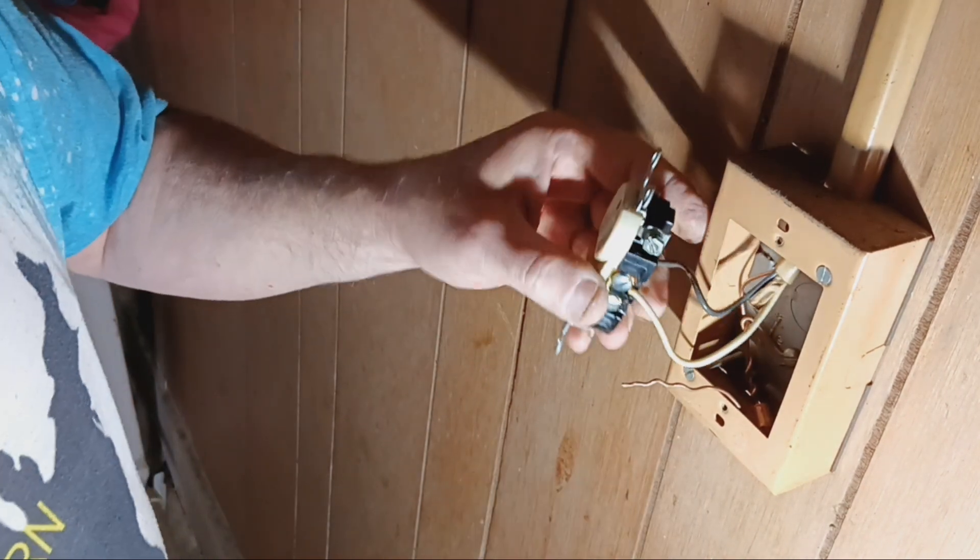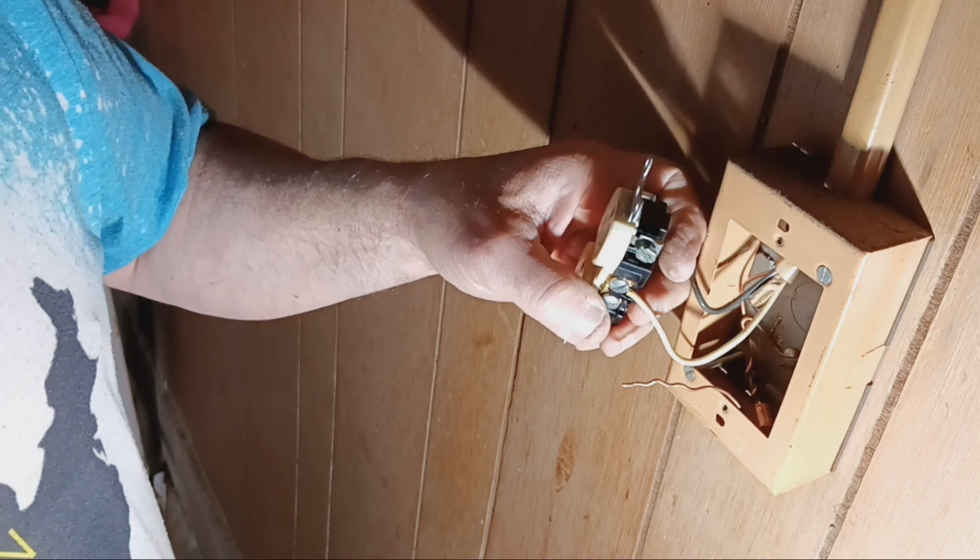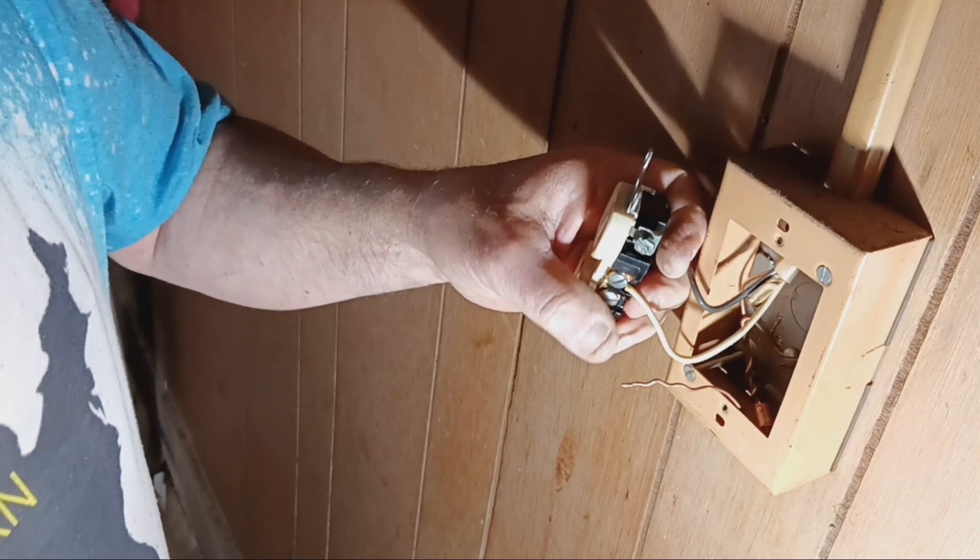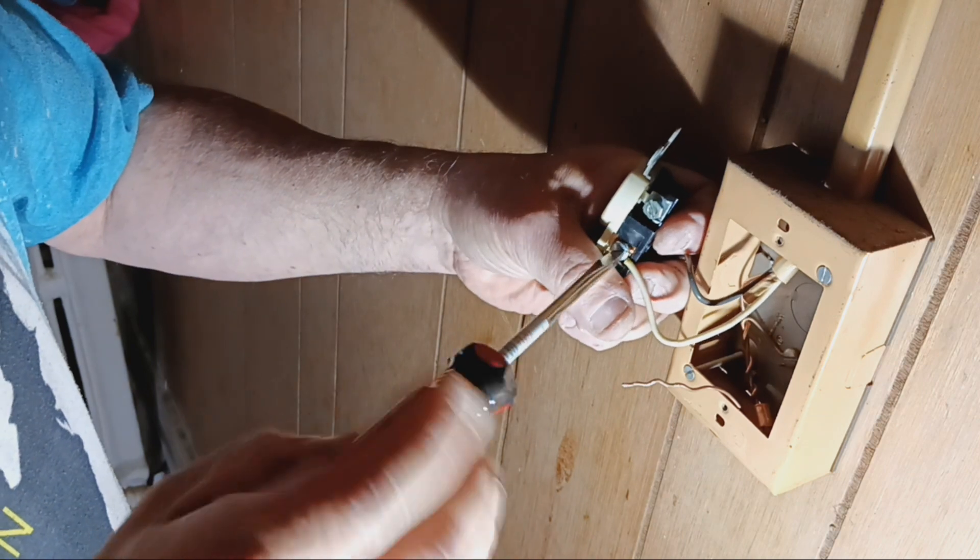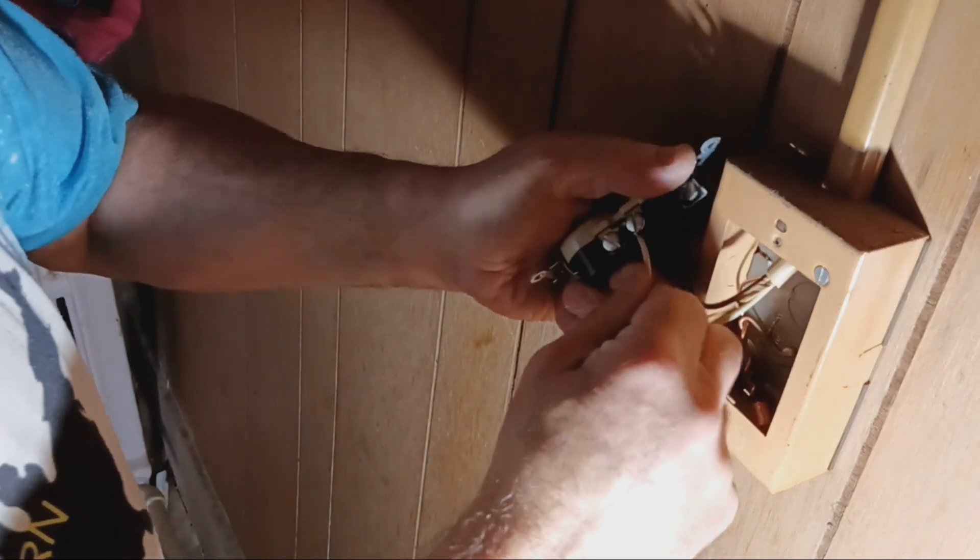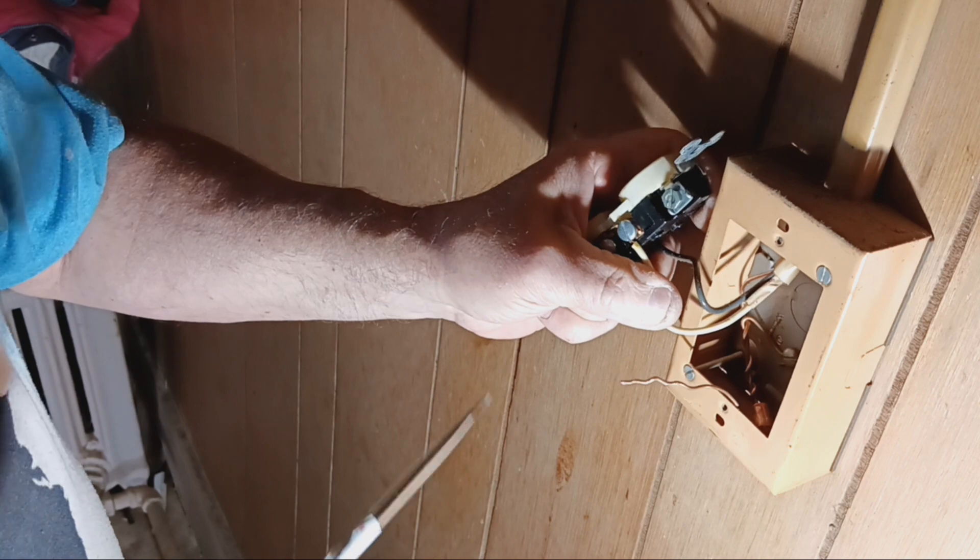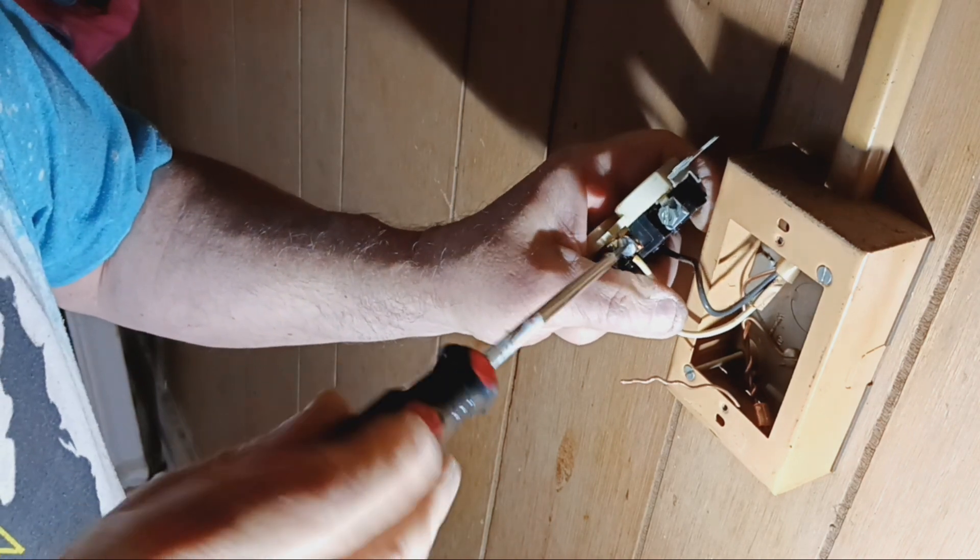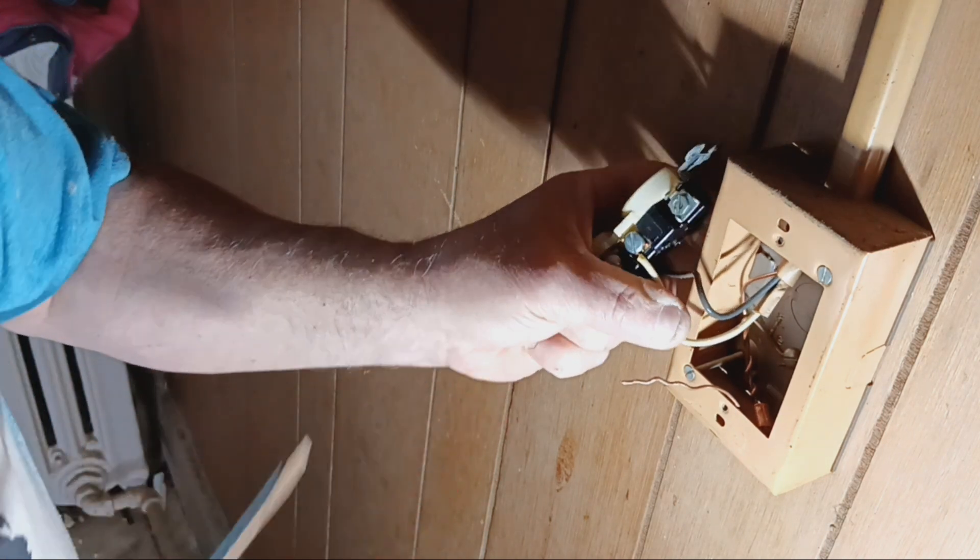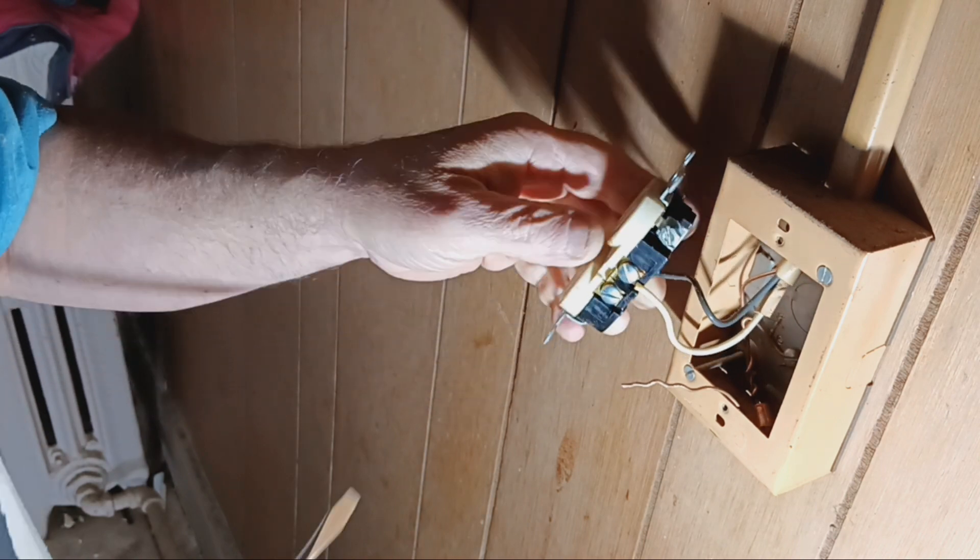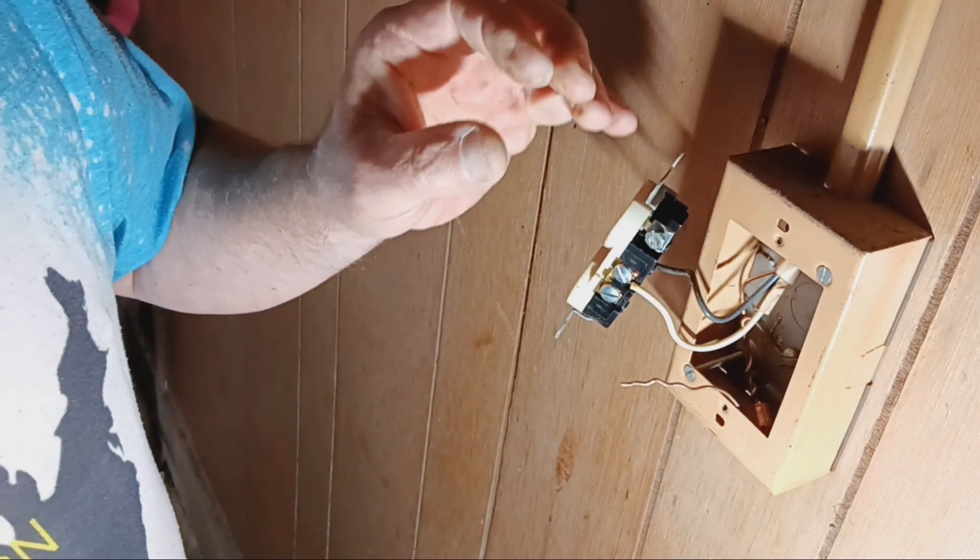Okay, so we'll look at our connections up here. Make sure they're good. Oh, that screw wasn't even that tight. I'll make sure our insulation is not caught under the screw head and it's wrapped around the right way, so I'll just tighten this back up. We have a good connection here. We'll put our ground wire around the green screw.